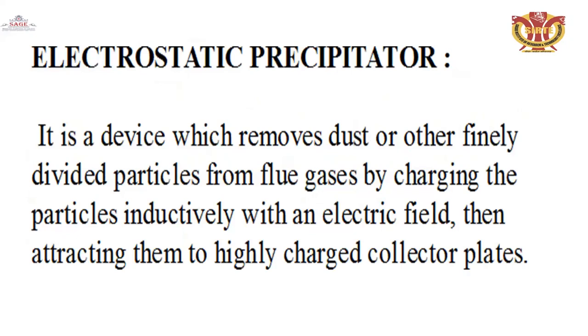The electrostatic precipitator is a device which removes dust or other finely divided particles from the flue gases by charging the particles inductively with an electrical field and then attracting them to highly charged collector plates. This removes dust and impurities from the flue gases.